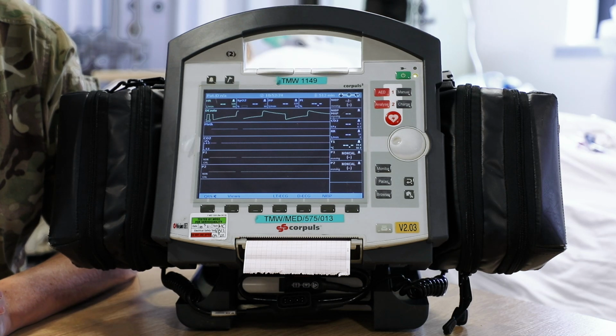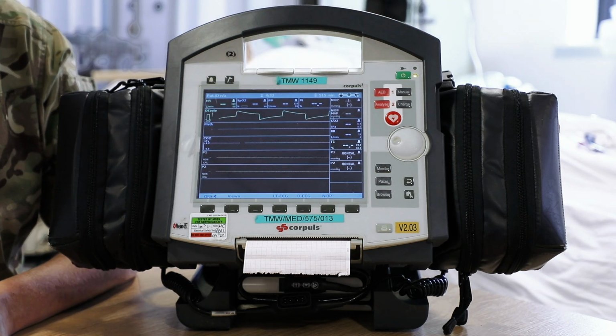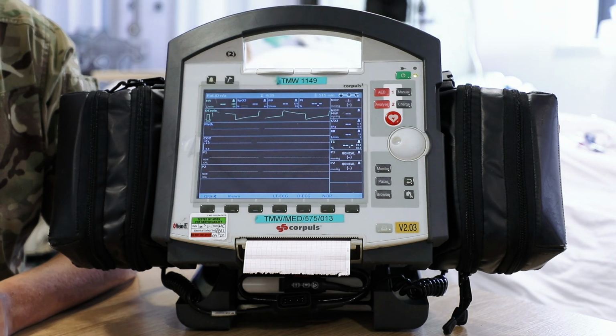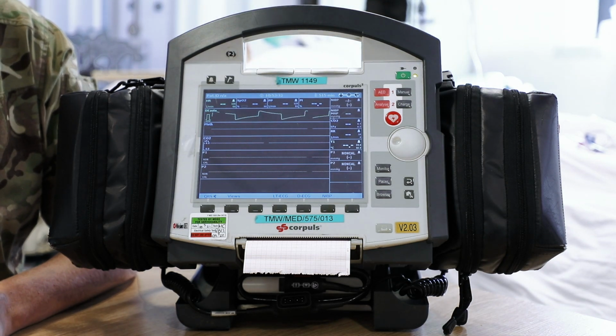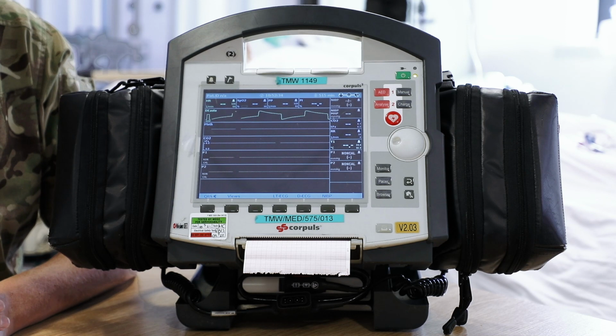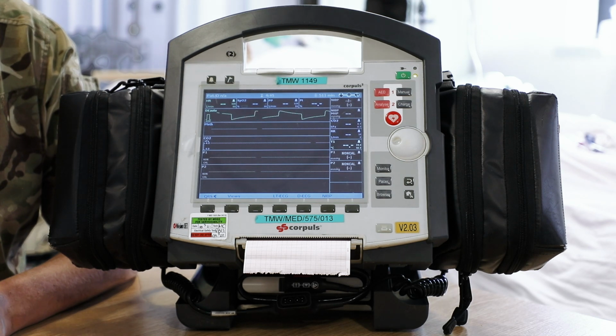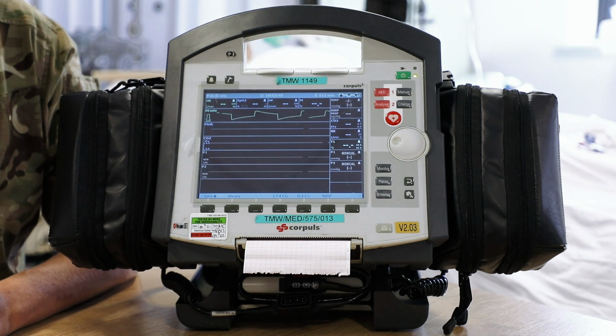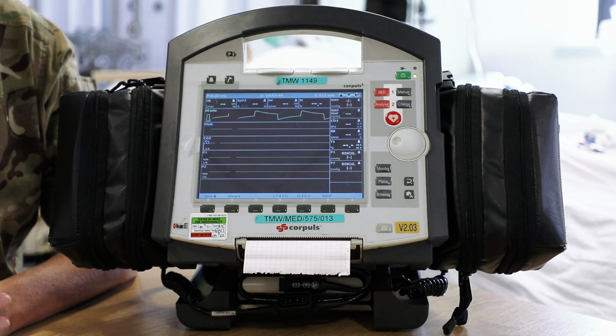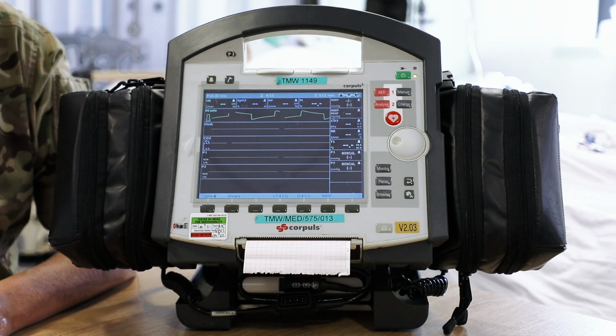Move on to checking the defibrillator, and there's a number of safety points that we need to bear in mind here. We're going to make sure that we never test the defibrillator when we're on our own, so make sure there's always someone around just for safety. Make sure the Corpuls isn't plugged into the mains, and when we're handling this red master cable, we're not going to handle it whilst the defib is armed, and I'll show you that as we go through.